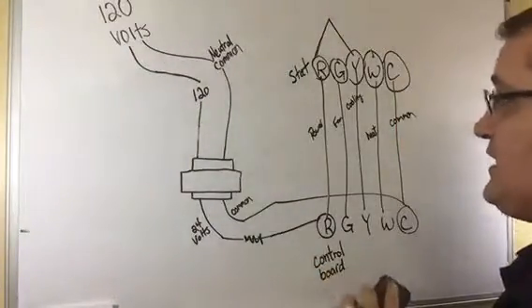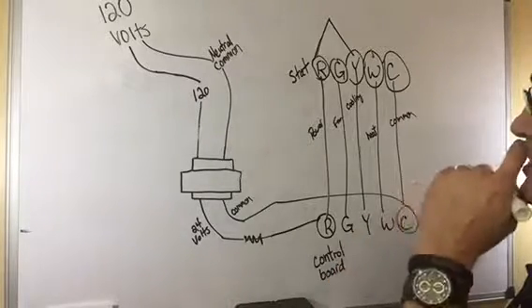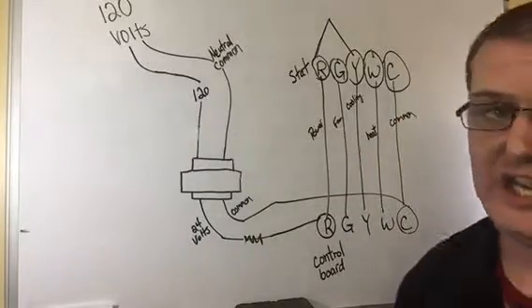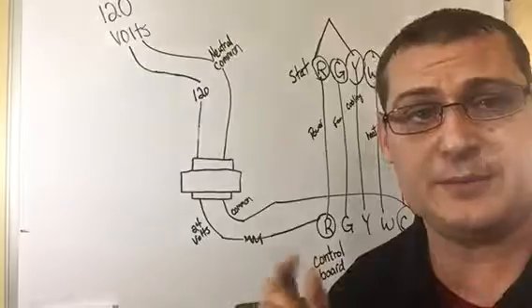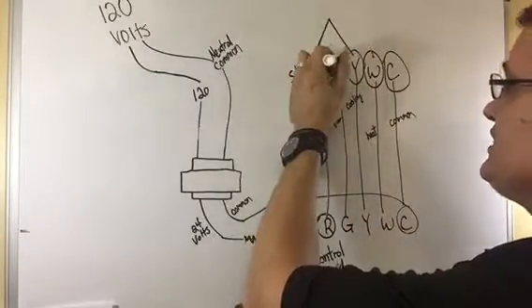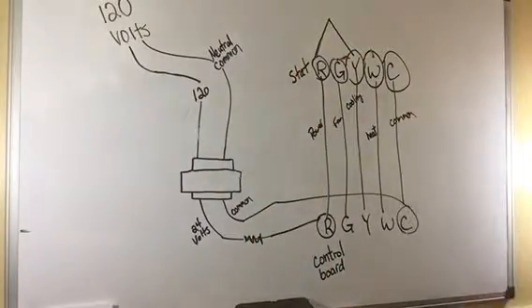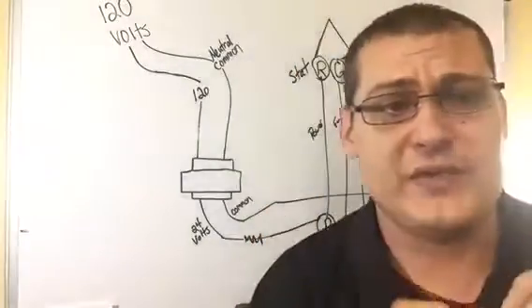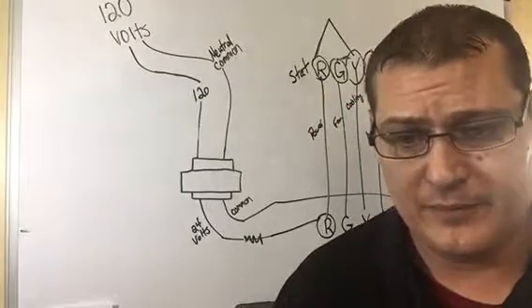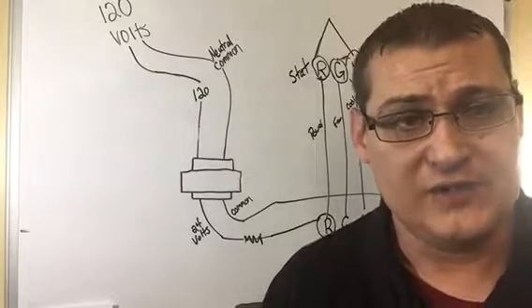That's just basic. Now, when it comes to G, Y and G with a call for cooling, they're the same terminal. So, as soon as Y gets power, G gets powered as well.